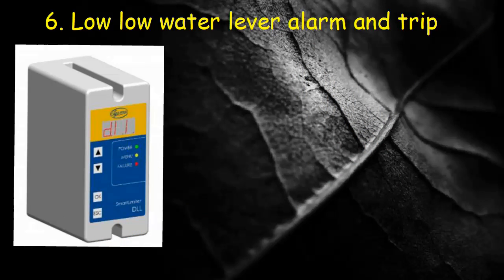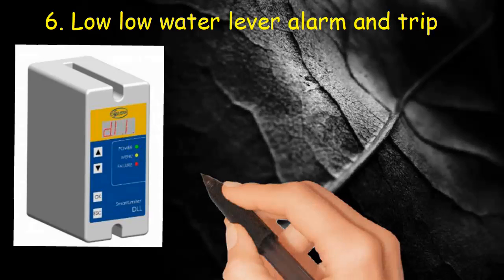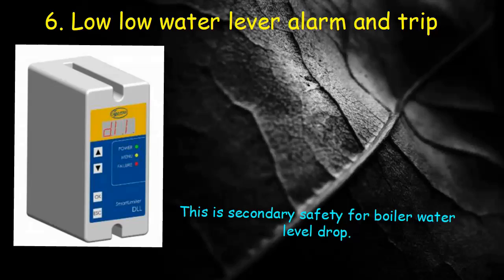Low low water level alarm and trip. If water level falls below low water level alarm, then burner will stop firing to prevent boiler shell from damage due to excessive heat from burner flame. This is secondary safety for boiler water level drop.